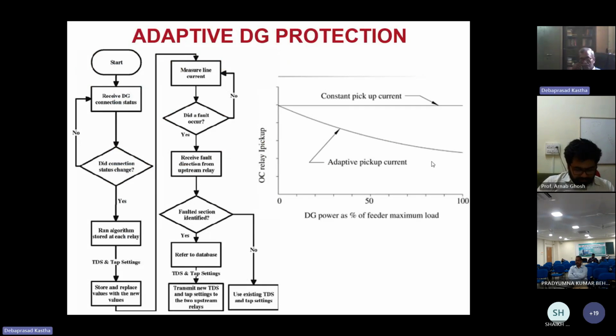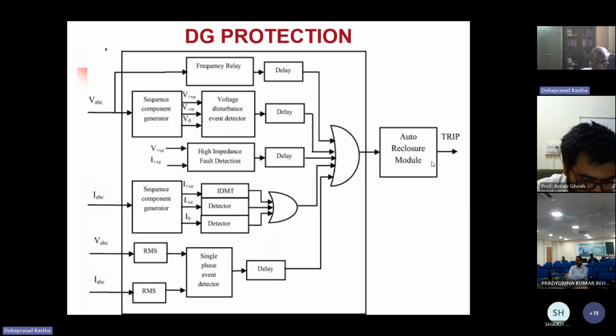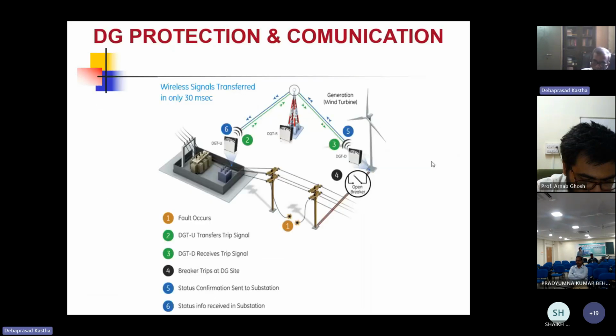Another thing is adaptive DG protection, the overcurrent relay. Instead of fixing a constant pickup current, you can adapt that pickup current depending on how much power the DG is sending. You can combine different types of protection because a single protection may not give you the optimum result. And you can also do it based on communication. That is, if there is a fault at one point, its effect will be felt in a different way in different parts of the distribution network. You collect the data from the whole network, then centrally compute it and arrive at a decision, and that is how you do the protection.